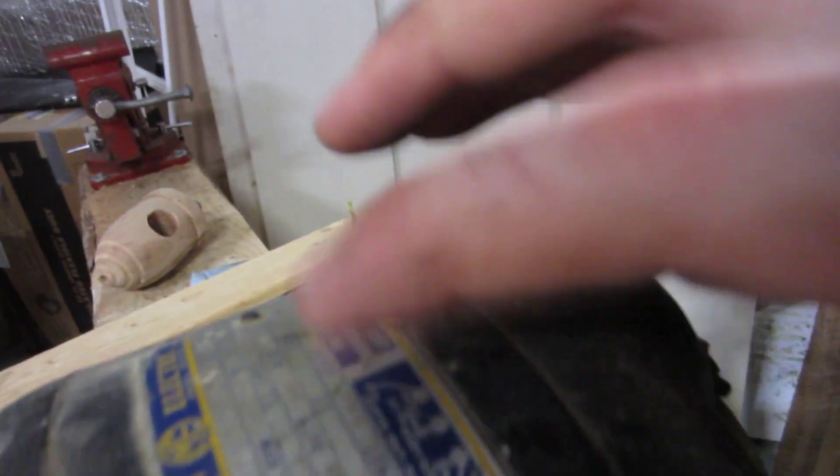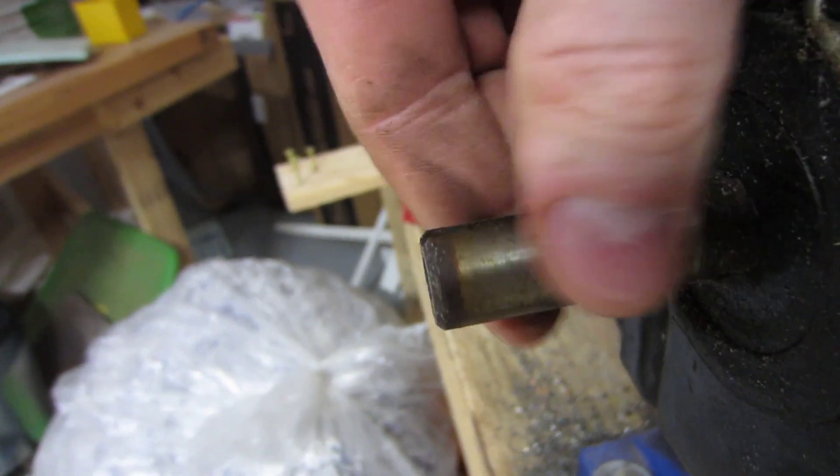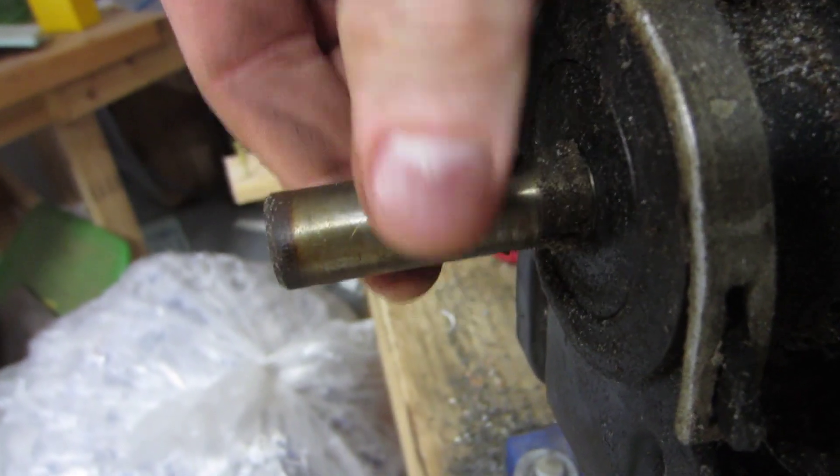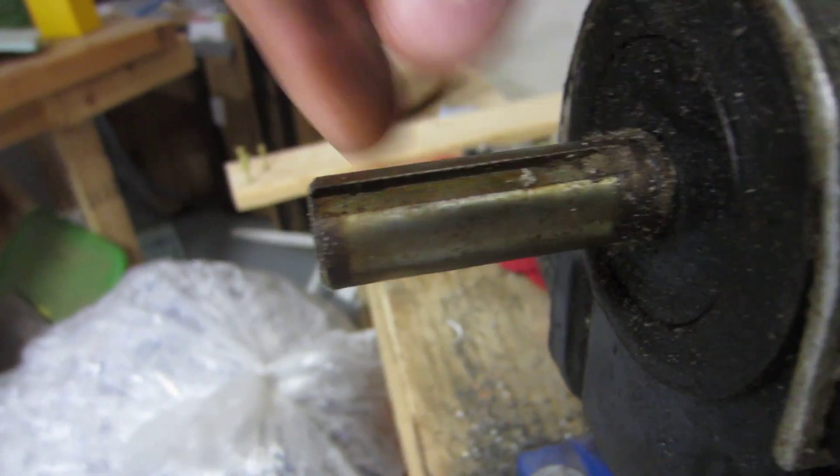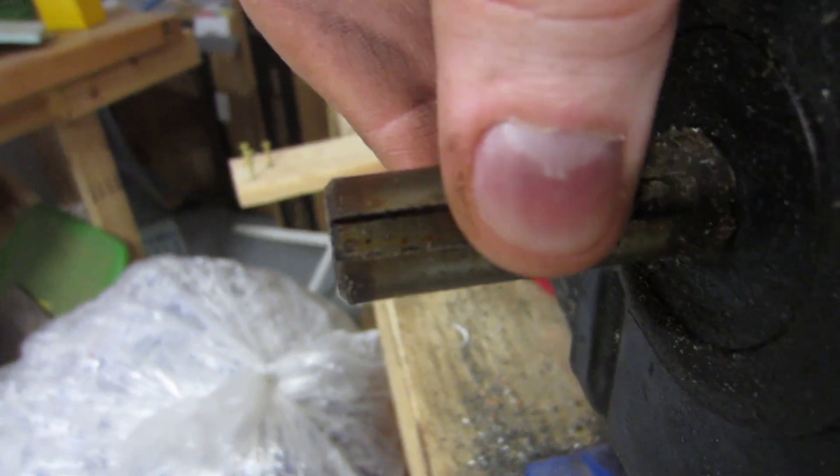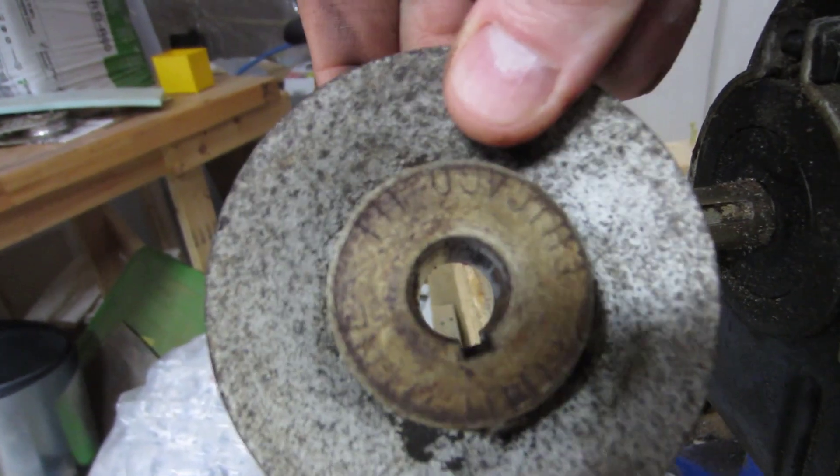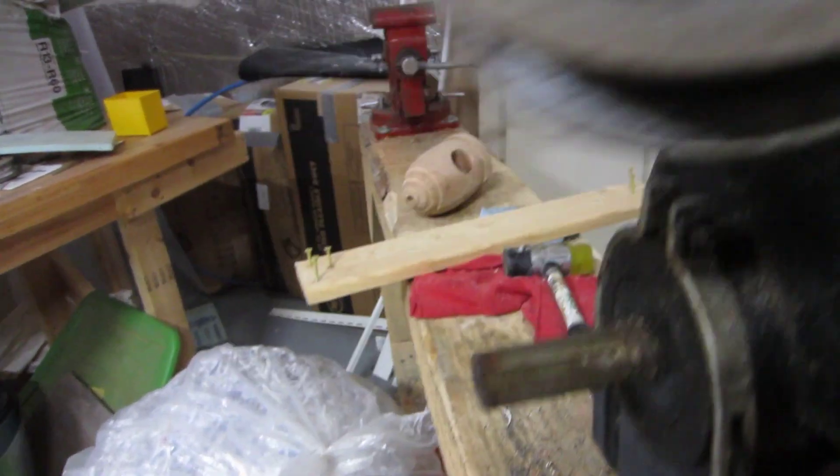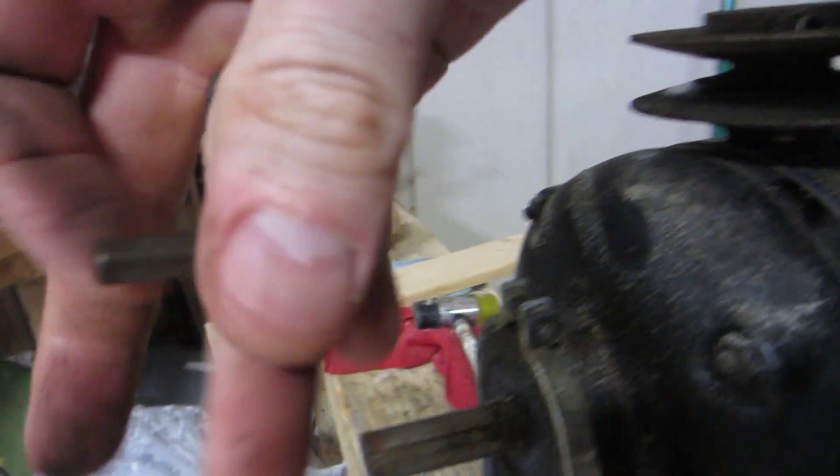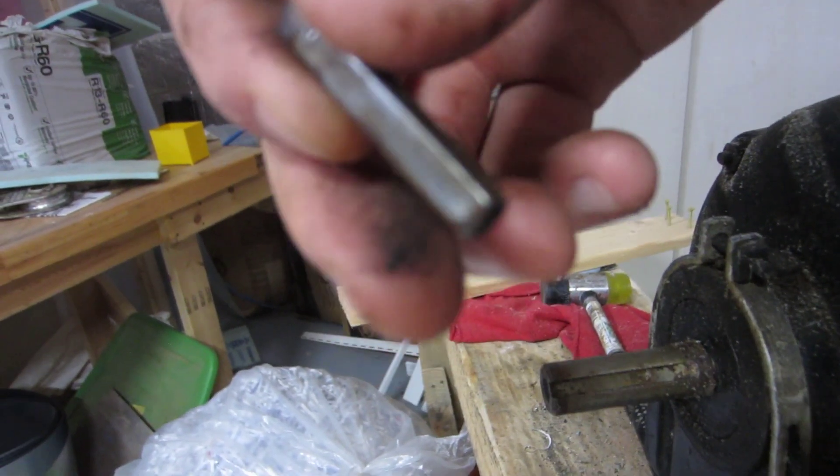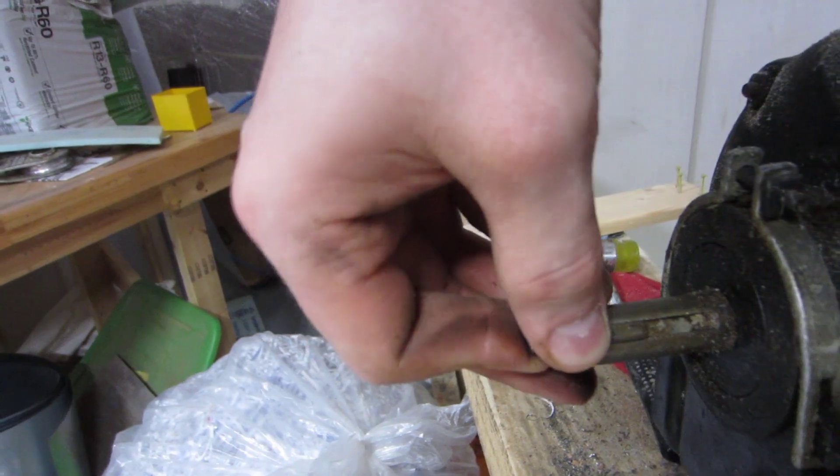The last thing is the diameter of the shaft, which may not be listed. You can measure it. I use some calipers, but in a pinch you could probably just use a tape measure. This is 5/8. There's also a keyway here, that's what that little channel is. In a pinch you could make a keyway, but it's kind of a pain. You can see there's another keyway right here on the pulley, and then lastly here is the key which is a square block of metal that binds the two together. That basically keeps the pulley and the shaft synchronous.